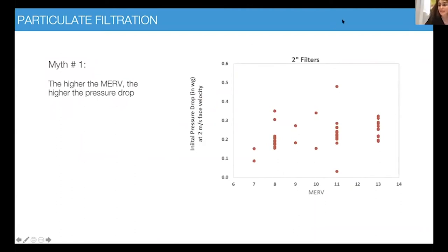But this, the first myth is that if you have a high efficiency filter, then you will have a high pressure drop. And I hear this from all my clients. Oh, I cannot put a MERV 13 because it's going to choke my system. This is not actually necessarily true. I show you here a database that I have. Now I have around 138 different filters. Each red dot is a unique filter.